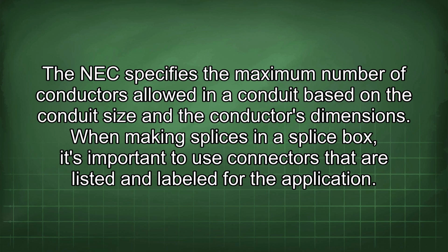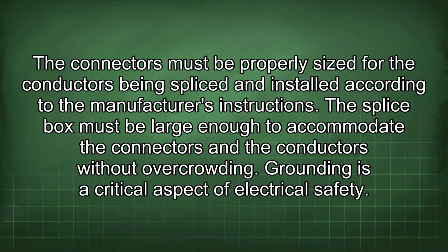When making splices in a splice box, it's important to use connectors that are listed and labeled for the application. The connectors must be properly sized for the conductors being spliced and installed according to the manufacturer's instructions. The splice box must be large enough to accommodate the connectors and the conductors without overcrowding.